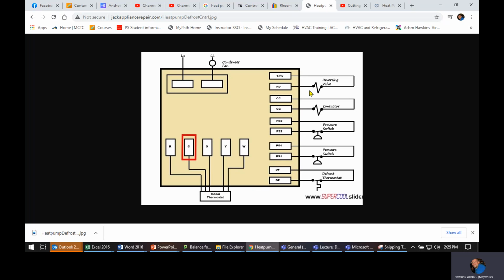Now, you'll notice these other things over to the side, and they're not always exactly wired like this, but it gives you a basic idea of all the things that this controls. So these are your inputs: red, common, orange, yellow, orange or blue, yellow or white. So you've got 5 wires coming into a basic single-stage heat pump. You've got 2 high-voltage wires. So what you'll see in lab and later on, what we're actually doing here on this condenser fan is we're breaking one leg of hot. So this isn't a low-voltage wire. This is high voltage. These down here are low.